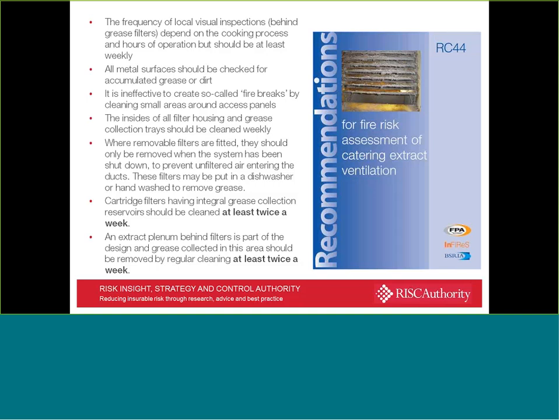Insides of all filter housings and grease collection trays should be cleaned weekly as a minimum. Where removable filters are fitted, they should only be removed when the system has been shut down to prevent unfiltered air entering the ducts. You may clean them by putting them in a dishwasher, or they can be hand washed to remove the grease. But it goes on to say, which is different to the guidance we've seen earlier, cartridge filters having integral grease collection reservoirs should be cleaned at least twice a week, and the extract plenum behind filters, being part of the design, and grease collection in this area should be removed by regular cleaning, again at least twice a week.